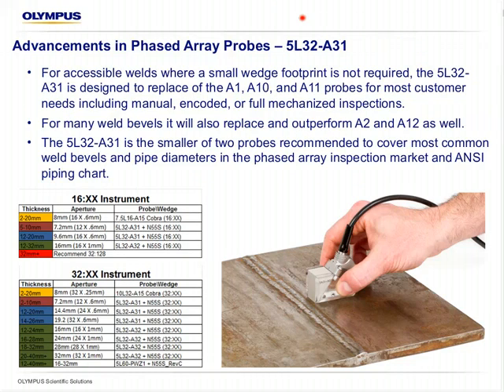The first of the three probes, and the smaller of the Weld series, is the 5L32A31. And for those of you who might not be familiar with the Olympus naming, that's 5 megahertz linear array, 32 total elements, and the A31, or the last alphanumeric, is a housing that gives us compatibility with the wedges. For accessible welds, where a small footprint is not required, the 5L32A31 would replace the A1, A10, A11 probes that most customers use for weld inspection for both manual, encoded, and full mechanized scanning. And for many welds, it will also replace or outperform the A2 and A12 for a few reasons we'll explain as well.